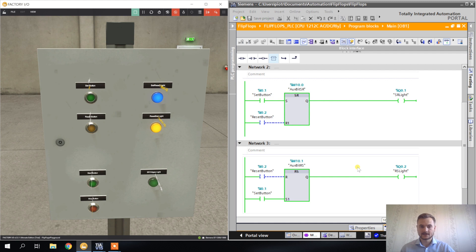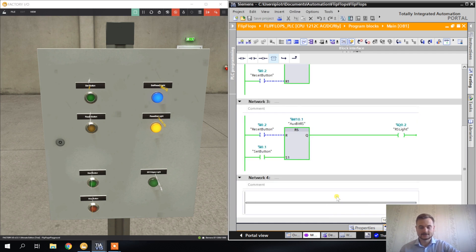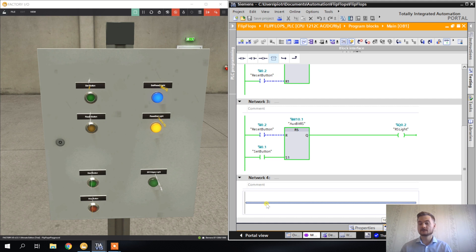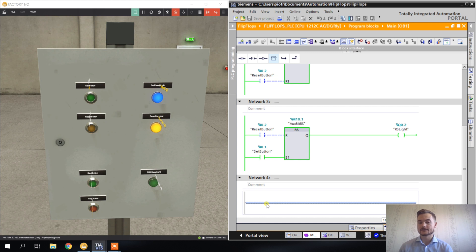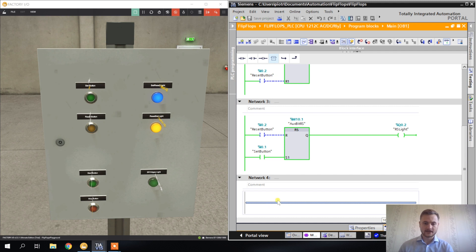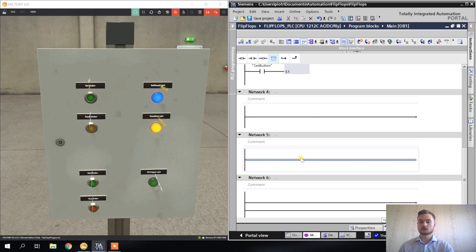Next I want to show you edges — positive and negative edge detection. Edges are instructions that give you a signal for only one PLC scan cycle. Whenever the state of an input changes from zero to one, we have a positive edge and the output will be one for one cycle. Whenever the state changes from one to zero, we have a negative edge, and if we're detecting the negative edge, the output will also be one for one cycle.